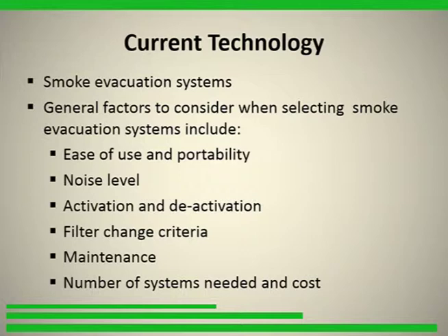We recommend that smoke evacuators should be put on before any smoke is produced, because once it goes up your nose, it's a failure. You don't get rid of it, and nothing will satisfy you. The filter change criteria, these filters, would you go back one, please? The filter changes usually now are mechanized with chips. These chips say after a certain amount of time, get rid of it and change the ULPA filter. But the best way to really know is put your nose right on the effluent side of the filter, and if you smell smoke coming out of there, it's time to change. The maintenance for most of these are pretty minimal. There aren't many things that go wrong with them.